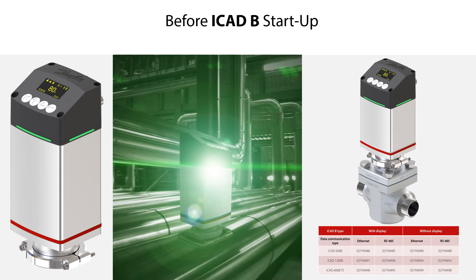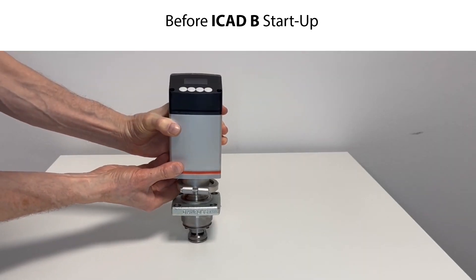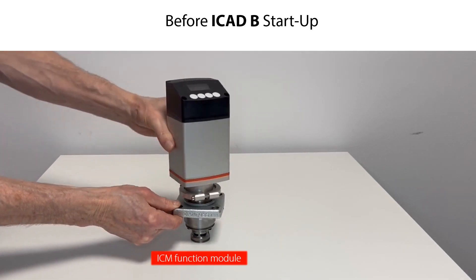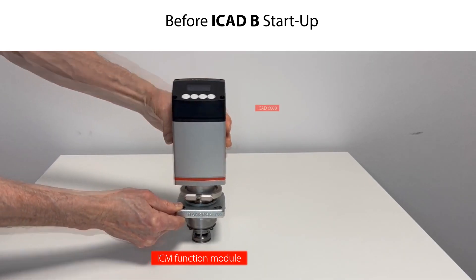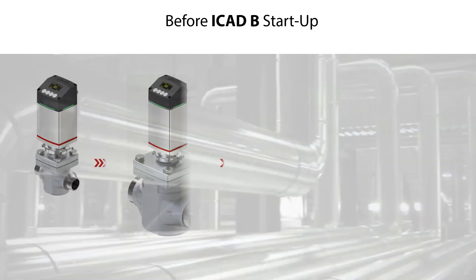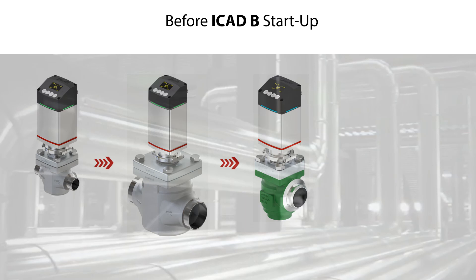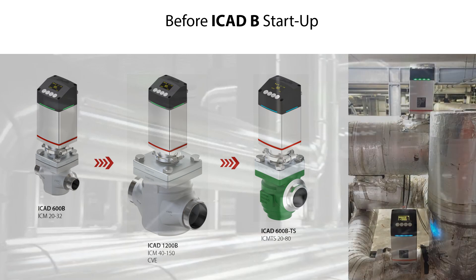Here is an image of the ICAD-B mounted on an ICM motor operated valve, with the available ICAD-B models specified. In this video, we demonstrate the ICAD-B setup and configuration using an ICM function module located on the table, and we mount the ICAD-600B model onto this ICM function module. The setup and configuration procedure is the same for all ICAD-B models and all suitable valves already located in a refrigeration system.